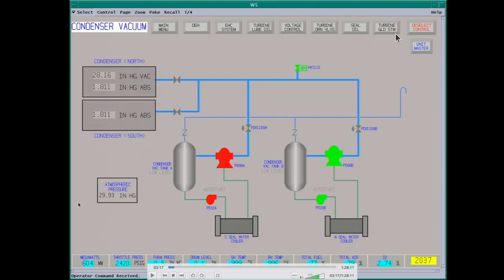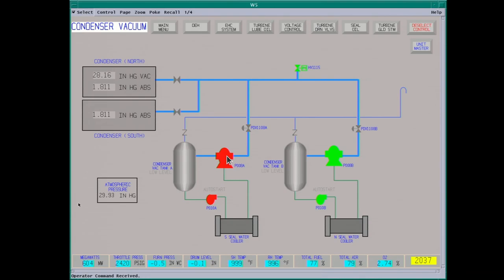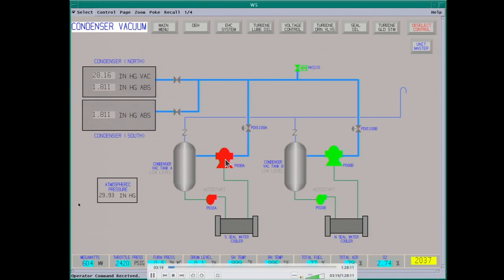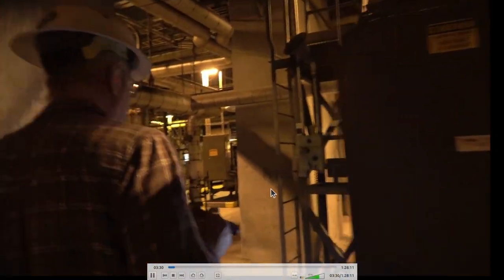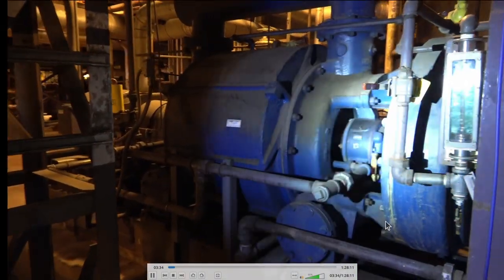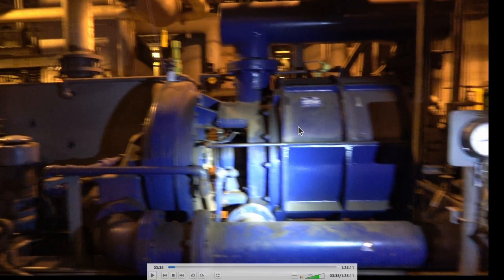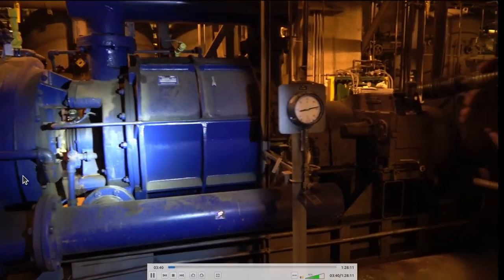These are the condenser vacuum pumps. It's critical to have good vacuum to get maximum efficiency out of your steam turbine. These are liquid ring vacuum pumps — there are two of them that run in series for high vacuum, and for startup they'll run in parallel to pull more vacuum, a hogging mode. They're very durable pumps since you're using water for sealing. You have a water collection tank, a heat exchanger on the side, a main pump, and a secondary for creating higher vacuum. Water comes in, is flung out, and actually does the sealing and pulls in the air.